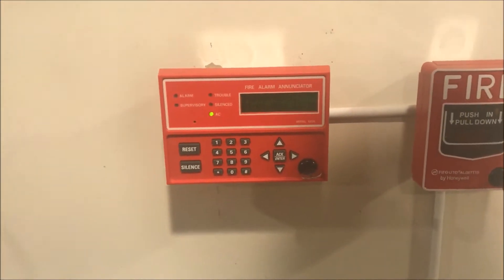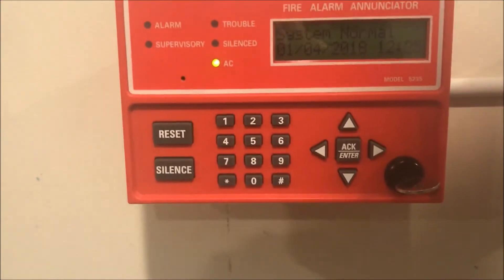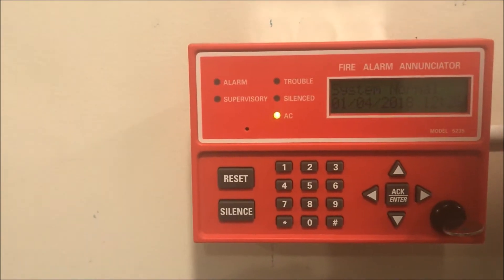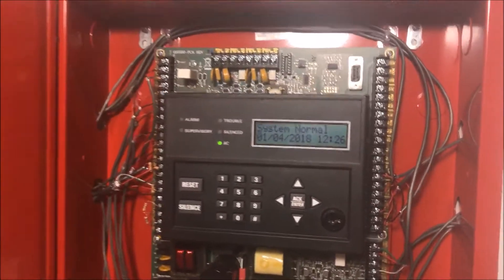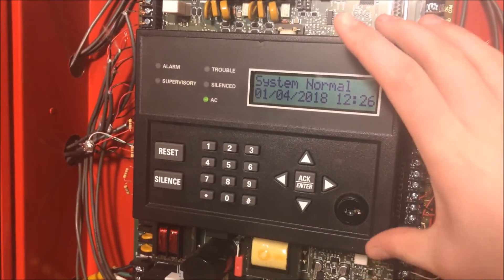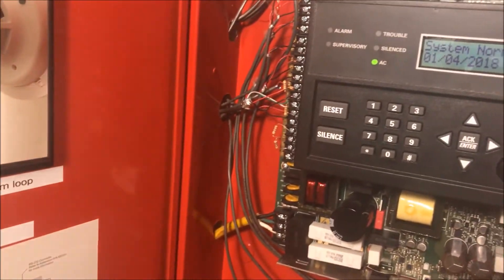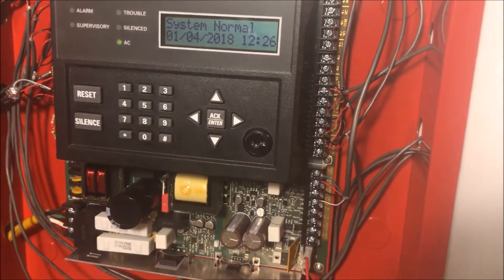So we are going to talk about what an annunciator actually is. If you notice, it does look very similar to my panel — to the control pad. That is because it basically is. It is the fire panel without all the wiring. Inside the panel there is that huge board and all the wiring terminals. Basically what the annunciator is, is just this black front part. You can program the panel and operate it remotely without having to actually be at the panel.